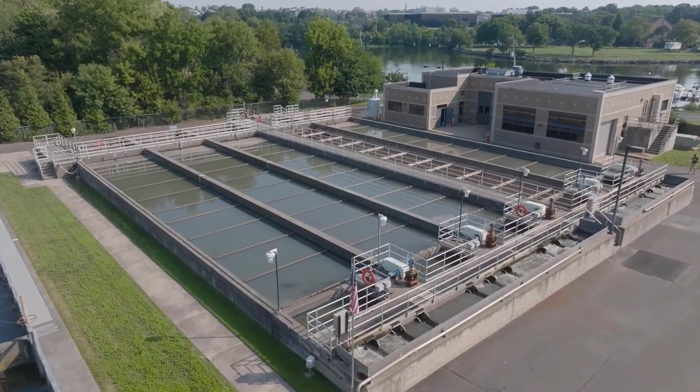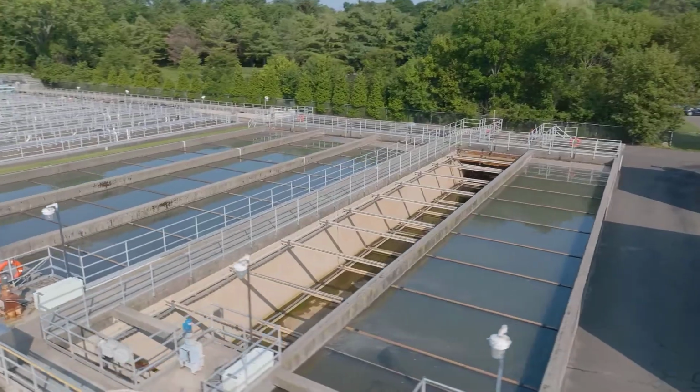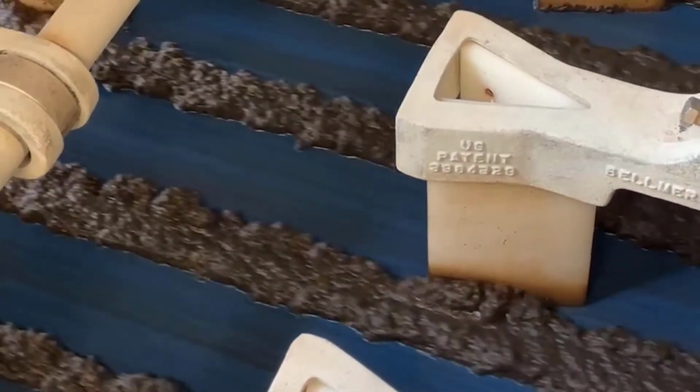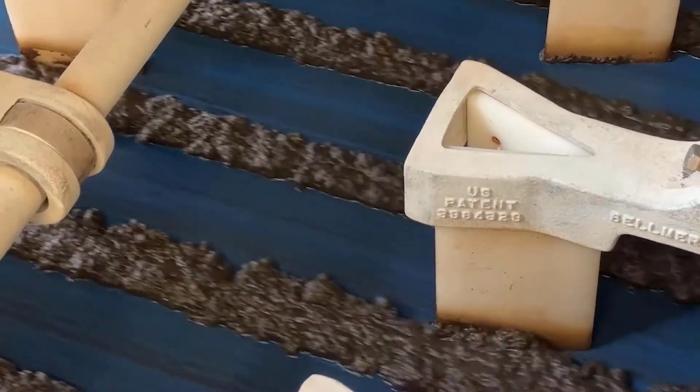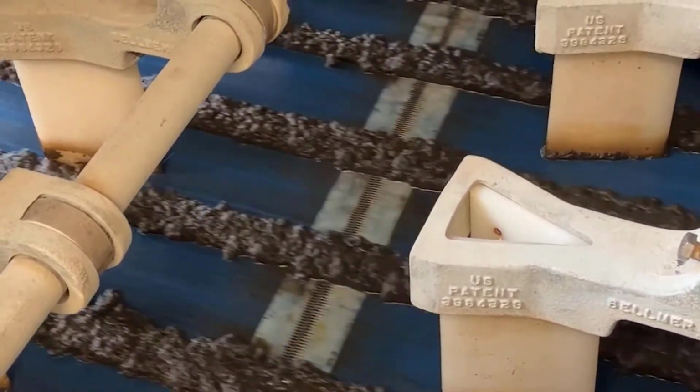The primary treatment of wastewater involves sedimentation of solid waste within the water. Water is passed through several settling tanks or primary clarifiers that separate water from contaminants. This is done to reduce the biochemical oxygen demand, BOD, and total suspended solids, or TSS, within the water. The resulting sludge from solids is then either disposed of as is or fed into a digester in which further processing takes place.